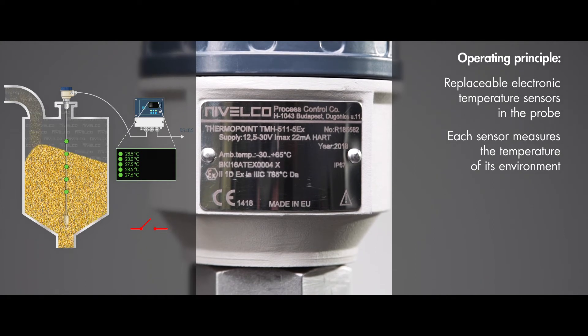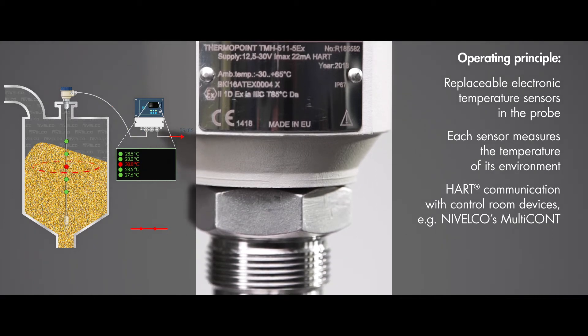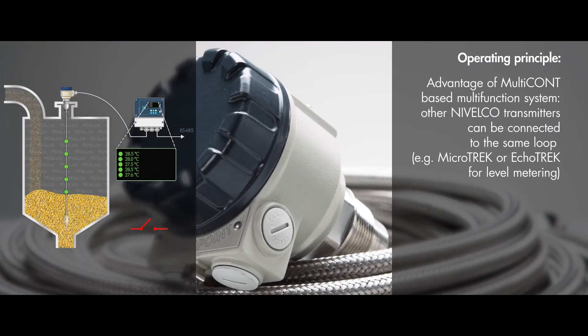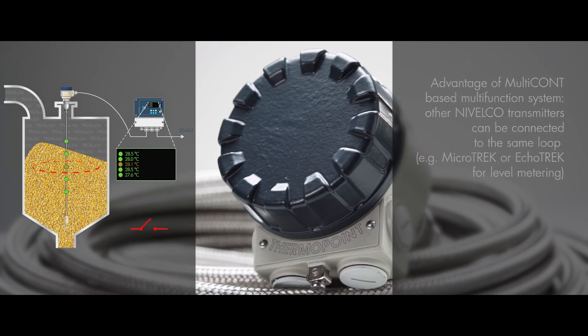The two-wire loop-operated transmitter head communicates through HART protocol with control room devices, such as Nivelco's MultiCONT or a PC. A notable advantage of a MultiCONT-based multifunction system is that, if a level measurement is needed, the appropriate level transmitter — for example Nivelco's MicroTREK or EchoTREK — can be connected to the same HART loop.